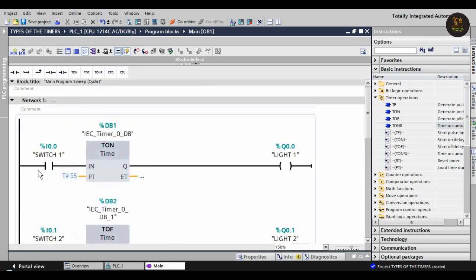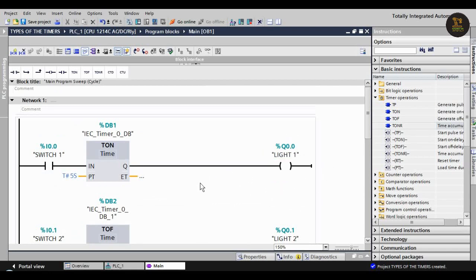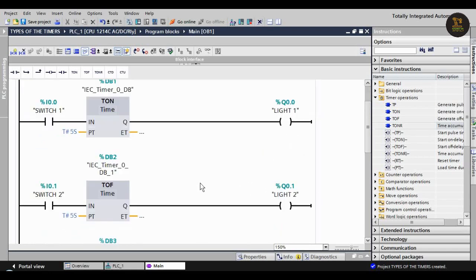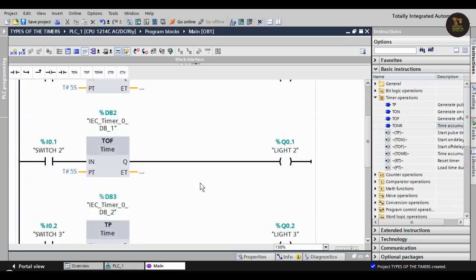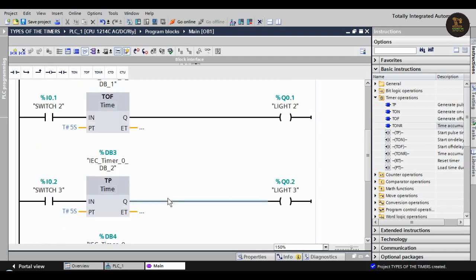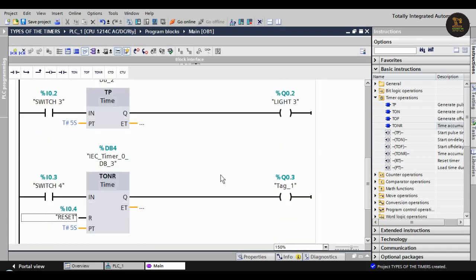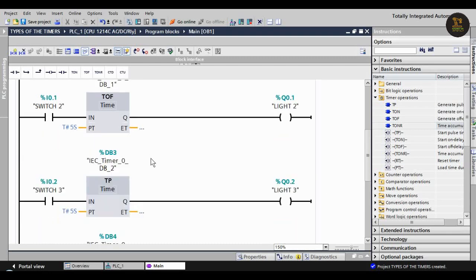Now once again we'll see - when we switch on, after five seconds delay, light one will glow. This is T_ON. In T_OFF, when we switch on, light two will glow. When we switch it off, after five seconds the light will turn off. In the pulse timer, when we switch on, light three will glow for five seconds only. When I0.4 is pressed, it will reset.